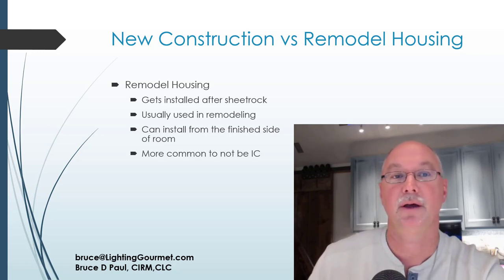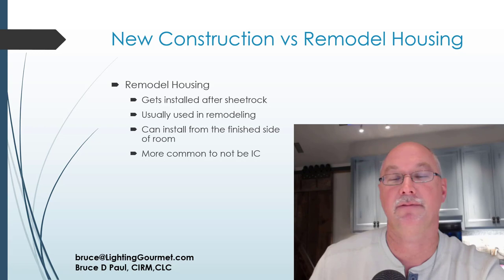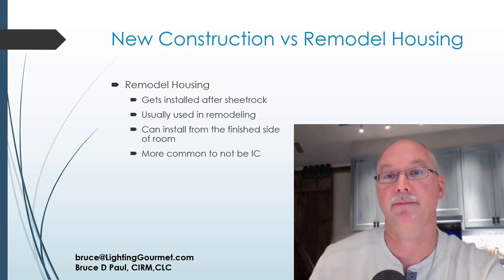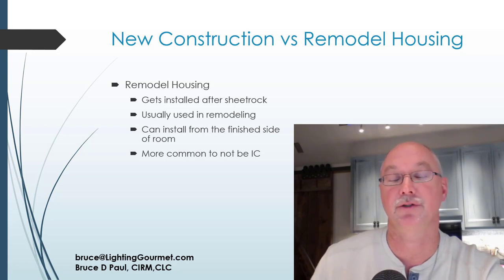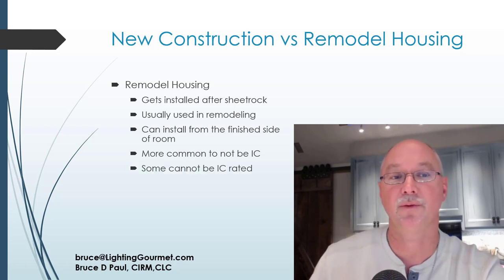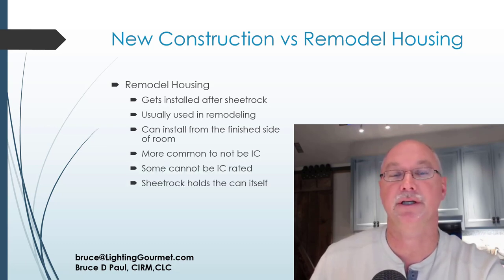It is more common to see a remodel recessed housing be non-IC. There are IC 5- and 6-inch cans, and there are also non-IC remodel cans in 5- and 6-inch. In 4-inch, you will not be able to find a 4-inch remodel can that is IC-rated — it's just too small, it doesn't have enough space. So to recap: 4-inch remodel cans are only going to be non-IC, while 5- and 6-inch remodel cans are available IC-rated.